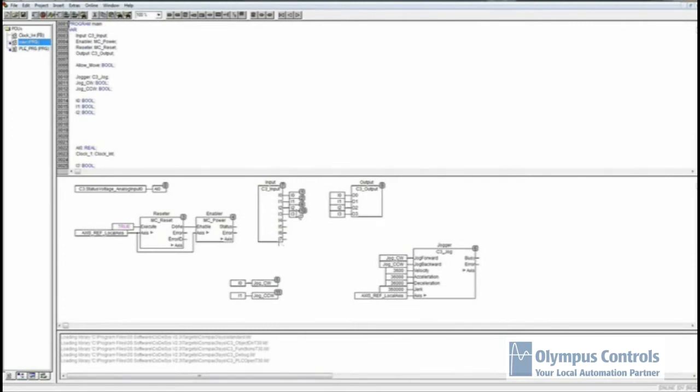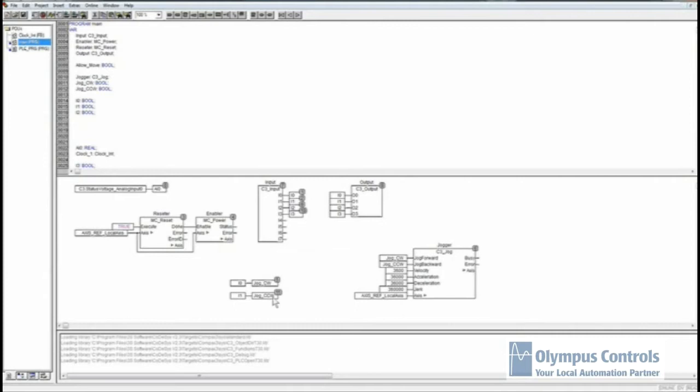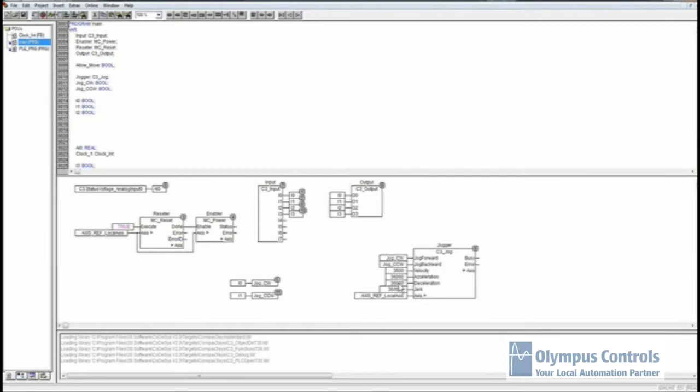Right here are my inputs. I just tied the very basic inputs I0 through I3. I then tied those directly to my four outputs that I have so that I can internally test and see what's going on. For nomenclature, I took the I0 input and put it to jog clockwise, and the I1 input to jog counterclockwise. The resetter and the enabler, these are just required in order to get it to run. Within this program, I created a jog function block. I used the velocity of 3600 degrees per second, and then an acceleration of 36,000 and deceleration of 36,000 degrees per second.